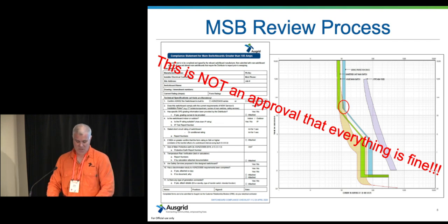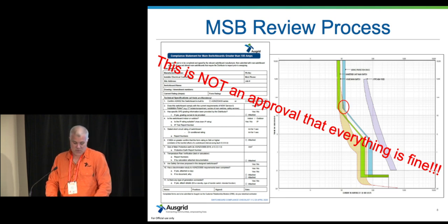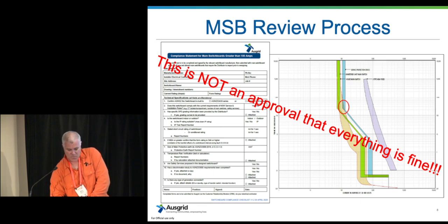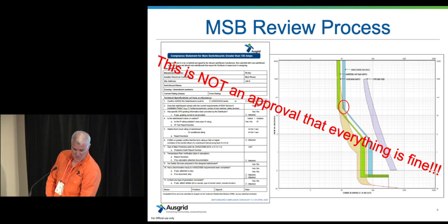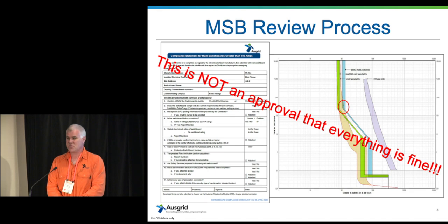We do come across the occasional discrimination study that we'll pick up on, and we'll go, you might need to look at that. This one in particular is not necessarily an issue to our network, but it's within the installation. We've got that slight crossover there. Depending on what that circuit breaker or fuse was doing within the installation, it may affect things. As you can see, it is crossing over the blue service protective device. So there is a chance that your SPD can actually function and switch off the whole installation rather than just that one component of it.